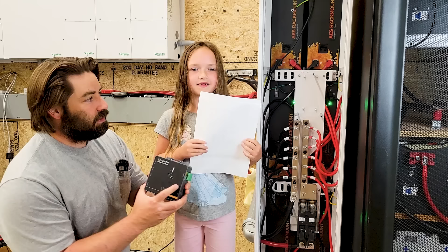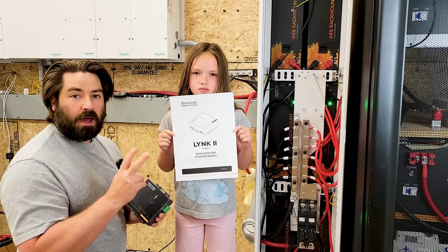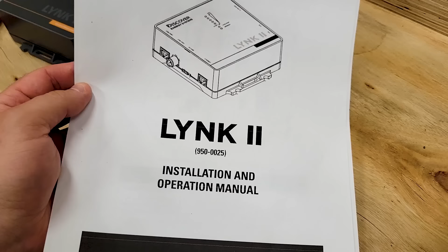Before we install this in the cabinet, we need to change some of the jumpers on the CAN bus and then check the firmware, so we need to download the manuals. I'll leave a link to the manual in the description below. There are two manuals you might be tempted to use—there's another one labeled a LYNK II for Schneider manual, but it turns out that has a little outdated information in it. Comparing the two, I found a little conflicting information, so I called Discover and they looked into it and confirmed this is the more up-to-date manual. So let's make sure we look at this one.